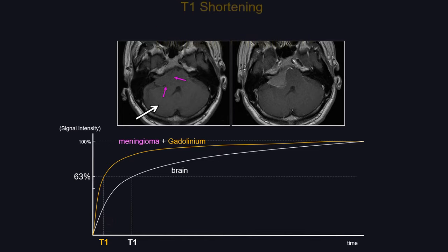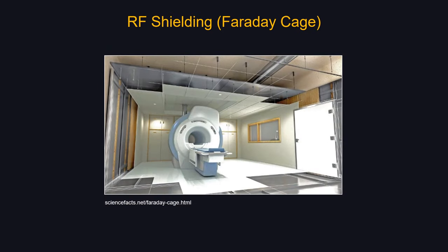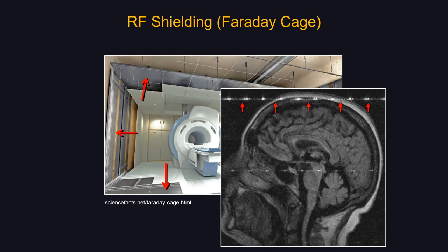Why do we call it an RF pulse? It's in the same wavelength as radio waves. That's why when you construct a new MRI suite, you put in a Faraday cage or RF shielding to block out unwanted external radio waves. If you don't have good RF shielding — due to a defect or an improperly sealed door — you will get a zipper artifact. Another common cause is interference from electronic monitoring equipment brought in with a patient.